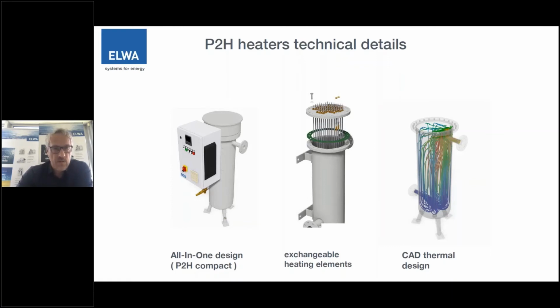So we have a design that is really proven, stable, and easy to exchange regarding the heating elements. It's a very compact design. The heating elements are resistor heating elements, and they can be exchanged without special tools. We do a very thorough thermal design to avoid any hotspots in the system, which leads to a longer lifetime of the heating elements.